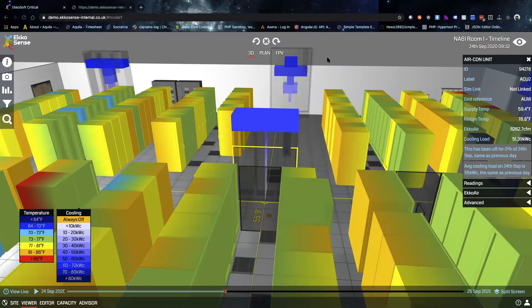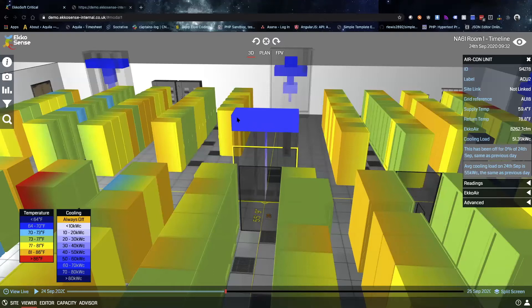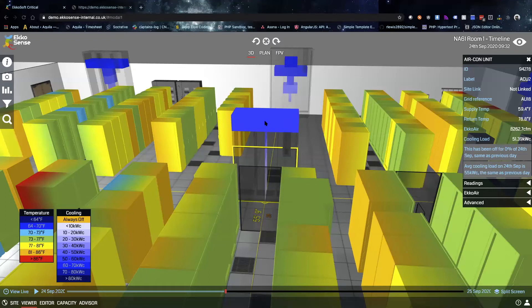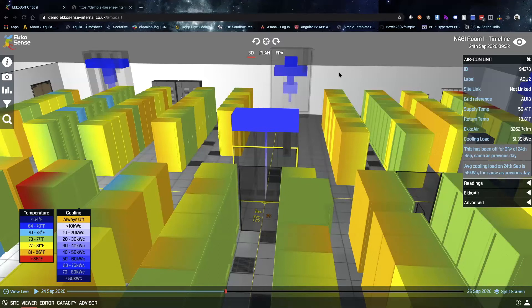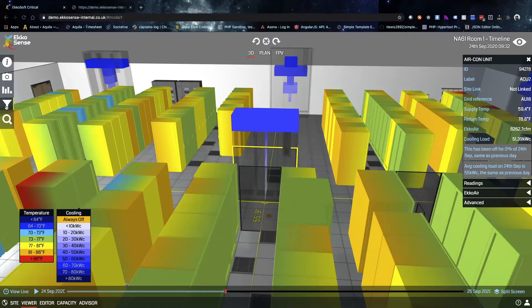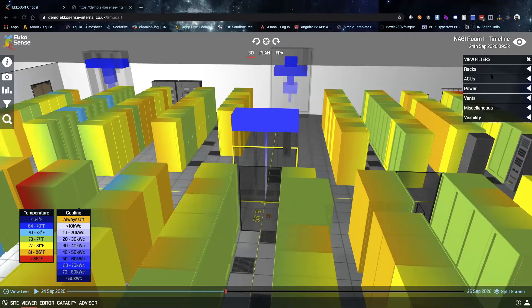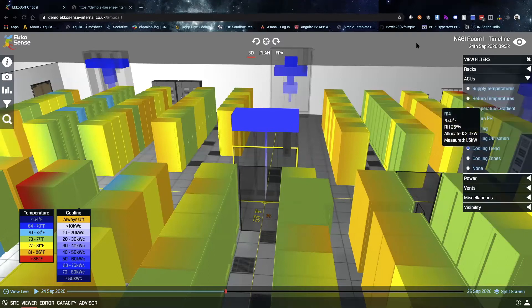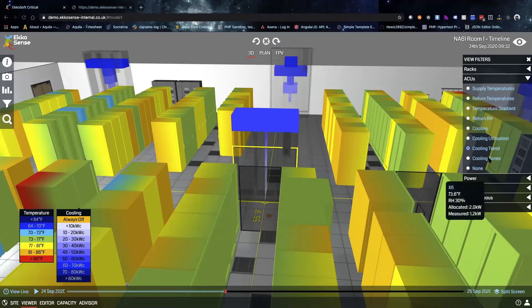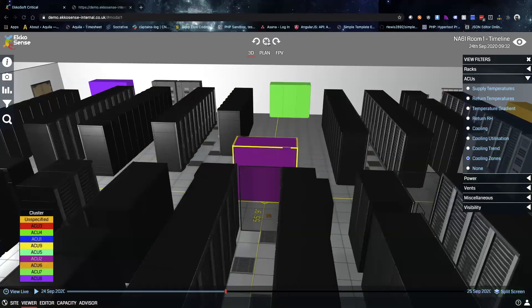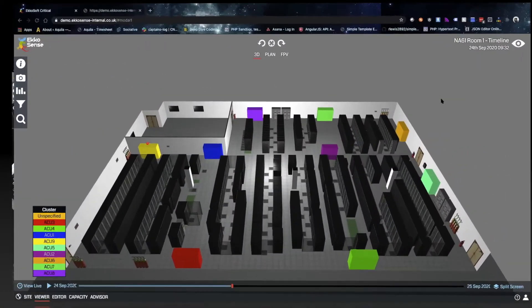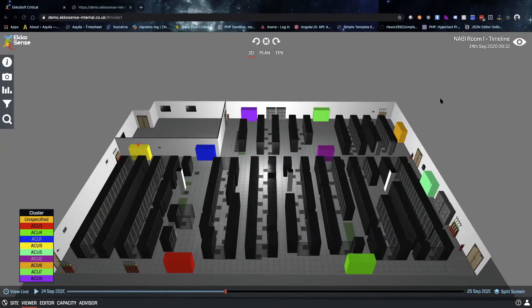This is very useful information in looking at where the cooling units are picking up load. For example, this cooling unit only has one bar. It has spent 100% of the time in the last 24 hours running at this high level of cooling capacity, so this cooling unit is running flat out doing its best to meet the set points but never able to achieve them. This information becomes really useful in identifying areas of the room where there is redundant cooling capacity and where there isn't.